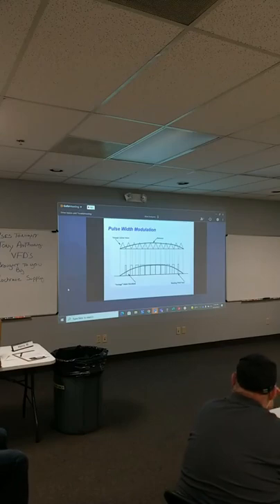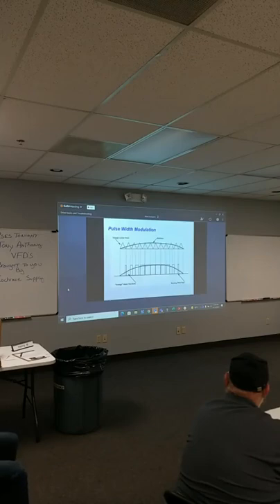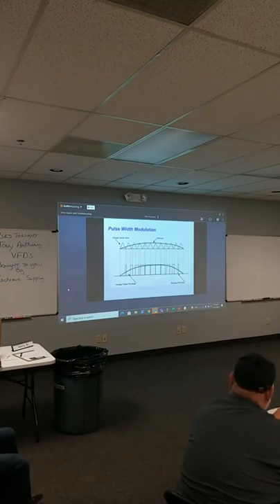So instead of seeing, on a 240 system, your peaks would be 240 to negative 240, so you're looking at 480. On 460, you'd see 920 if it's a pure sine wave. Because this is pulsing DC out to the motor, instead of 920, you might see 1100 volts in that motor. The further the motor is from the drive, the worse it gets. If you have that motor 5 foot from the drive, it might be 1,000, 1,100 volts. Move that motor 500 feet from the drive, same exact motor, same exact drive, but because of the distance and the way DC works over distance, you may see 1,400, 1,500 volts in that motor.